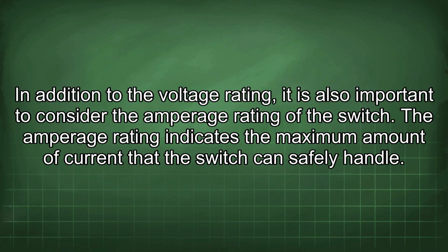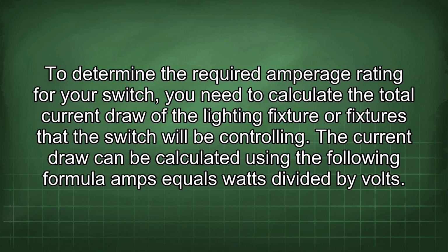In addition to the voltage rating, it is also important to consider the amperage rating of the switch. The amperage rating indicates the maximum amount of current that the switch can safely handle. To determine the required amperage rating for your switch, you need to calculate the total current draw of the lighting fixture or fixtures that the switch will be controlling.